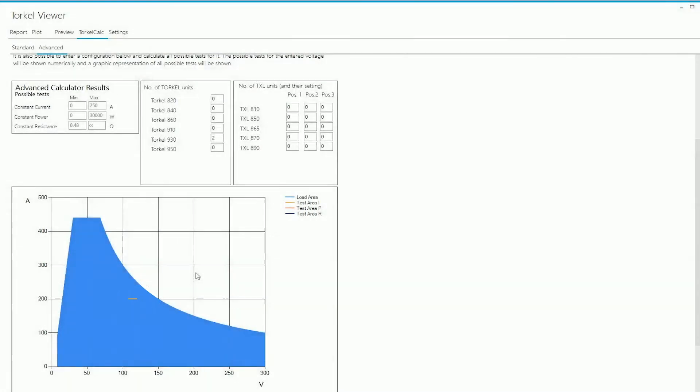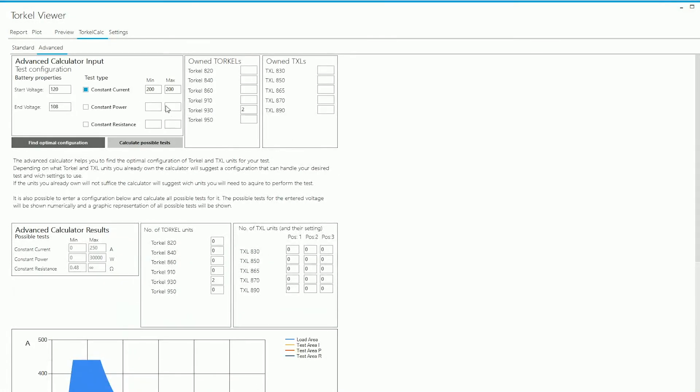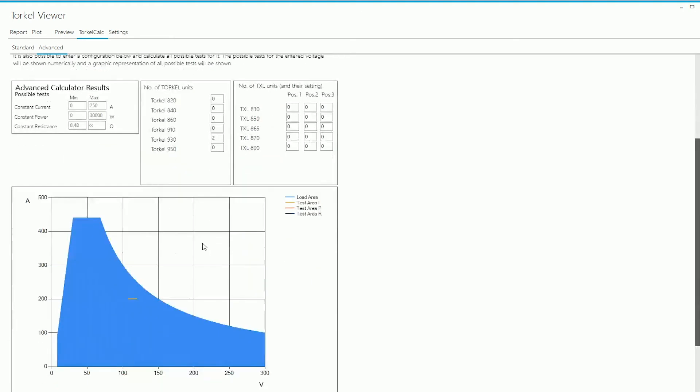I can see a little yellow line here and that yellow line corresponds to the test that I selected initially over here. So I mentioned a constant current of 200 amps and I mentioned that the voltage would start from 120 volts and would drop down to 108 volts during the course of this test. And that's what this line corresponds to. Since the test area lies within the load area, I know that the test configuration that's shown here would be able to run the test.